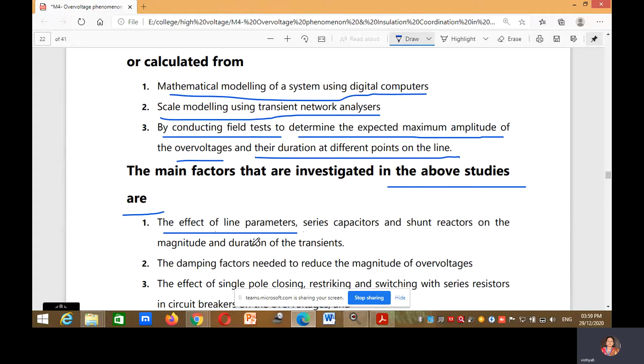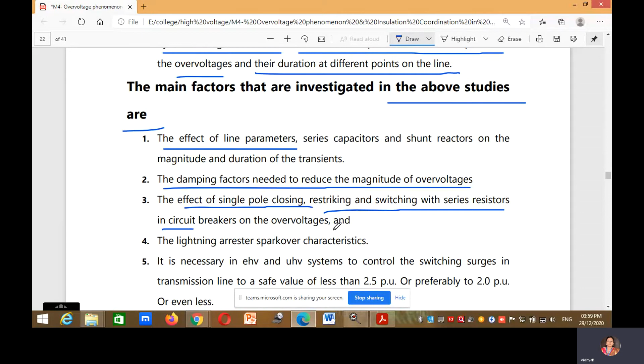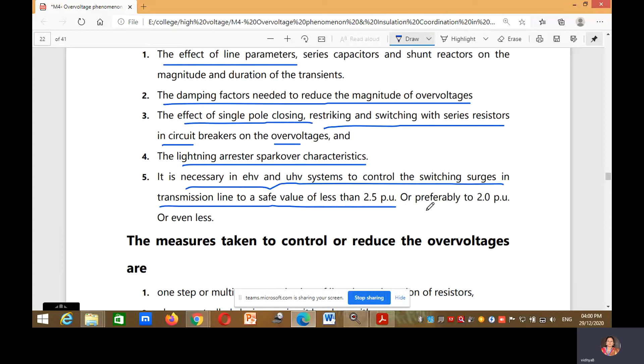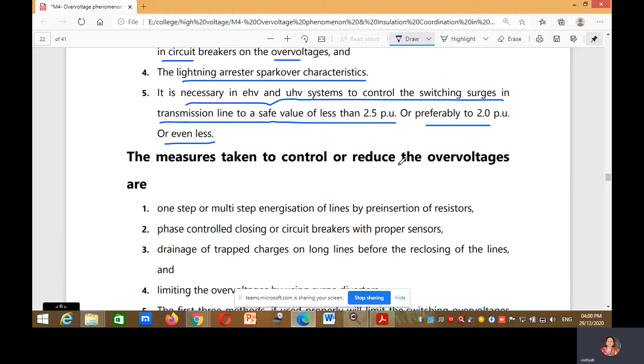Next is the damping factors needed to reduce the magnitude of over voltages. The effect of single pole closing, restriking, and switching with series resistors in circuit breakers on the over voltages, and the lightning arrestor spark over characteristics. It is necessary in extra high voltage and ultra high voltage systems to control the switching surges in transmission lines to values of less than 2.5 pu, or preferably 2 pu or even less. Next are the measures taken to control or reduce the over voltage.